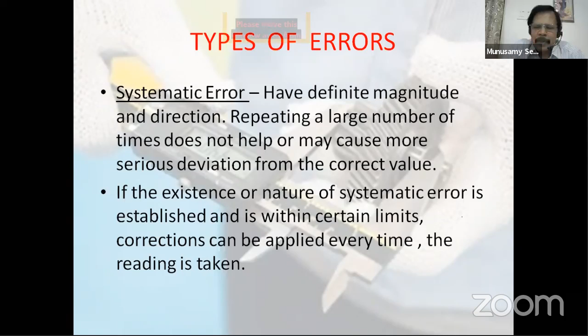And how do you get errors? Because you designed or got an instrument and then you're using it. How do you say the errors are coming? So the sources of error, obviously the first one, is aging, wear and tear. This is systematic error. Either the reading will keep on reducing from the correct reading, or it will keep on increasing from the correct reading. So this is systematic error arising out of the frequent use of the instrument. We call it going out of calibration.